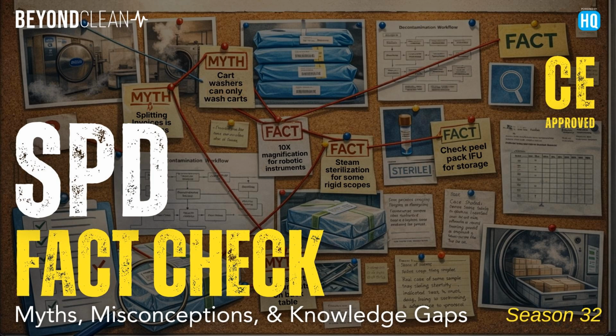The knowledge gap in particular that we're wanting to talk through today, though, has to do with sterilization. And it's always been one of the great SPD mysteries to me that you have these rigid endoscopes that all kind of have the same appearance. You know, they have similar construction. Yeah. Some of them, you read the IFUs, say that they've got to only be low-temp sterilization, typically going in our hydrogen peroxide sterilizers. But then there's a handful of them, particularly the smaller ones, like our arthroscopes, that for whatever reason at the facility I was at, could go in the steam sterilizer. Yeah. And that always mystified me.